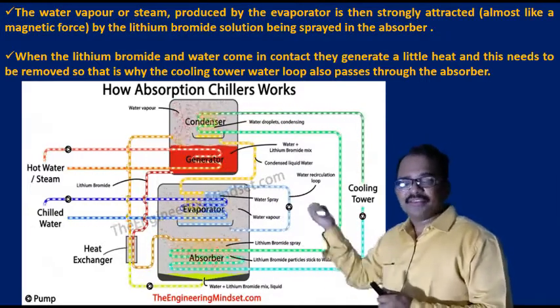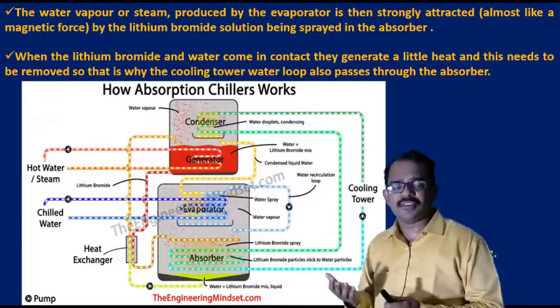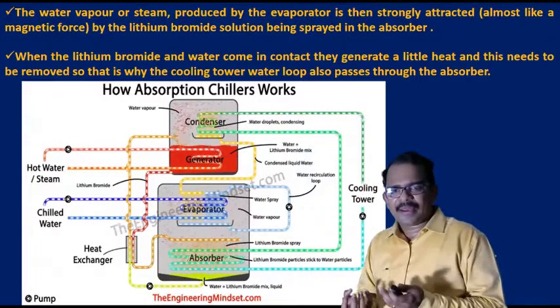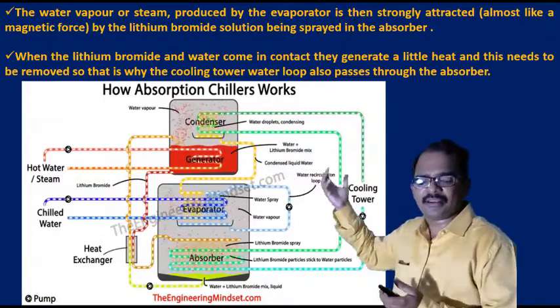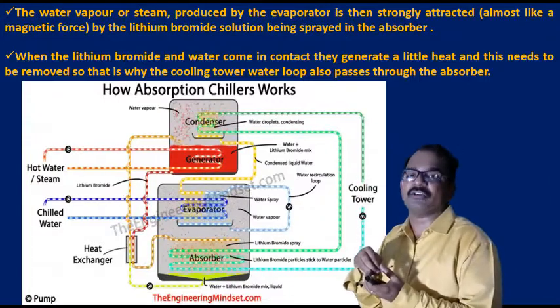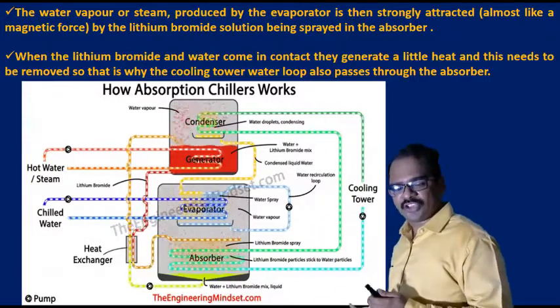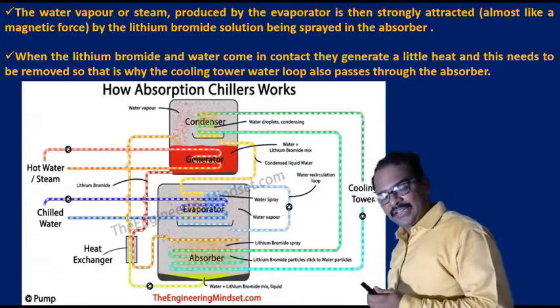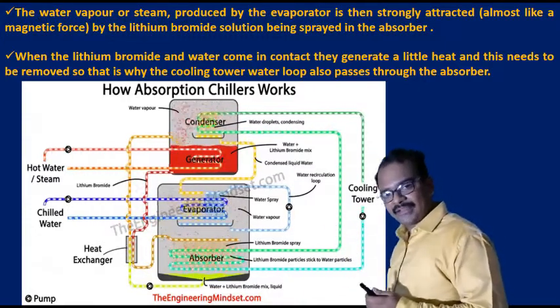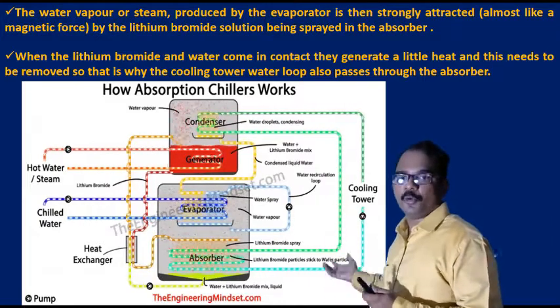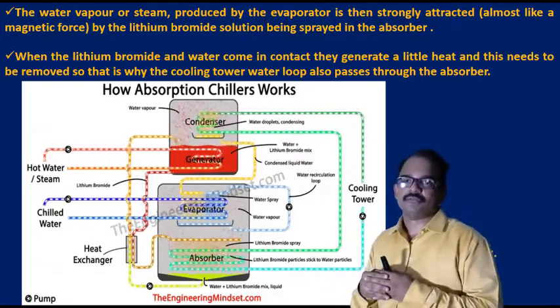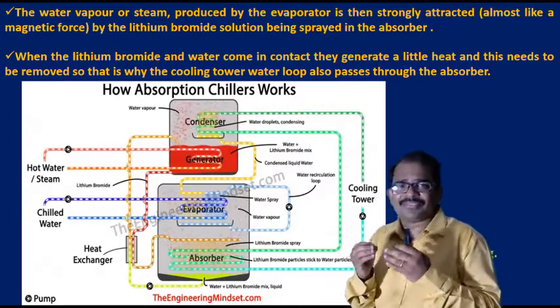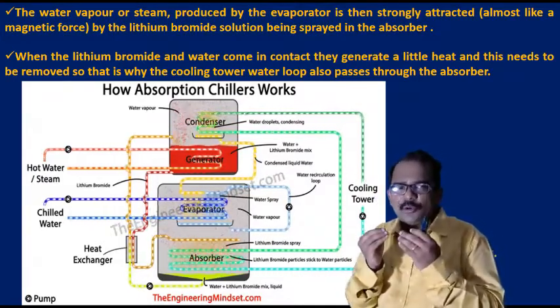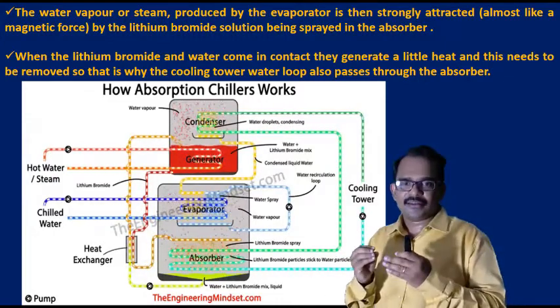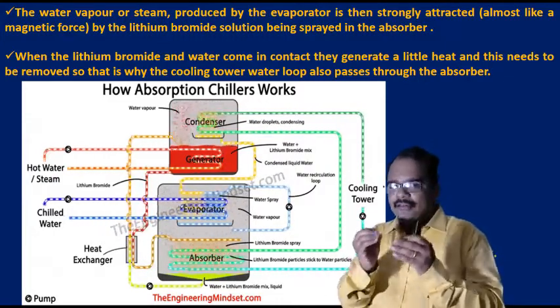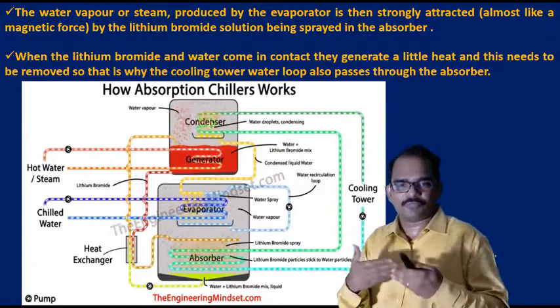Right. So this is the second concept which we have seen. The lithium bromide has a strong affinity towards water vapor, and when they come in contact, they will mix with each other perfectly. Now what happens in the bottommost chamber? We have the water vapor as well as the lithium bromide, so both will mix with each other. When both mix, they generate a little amount of heat, and that heat needs to be removed from the absorber in order to improve the efficiency of the system.